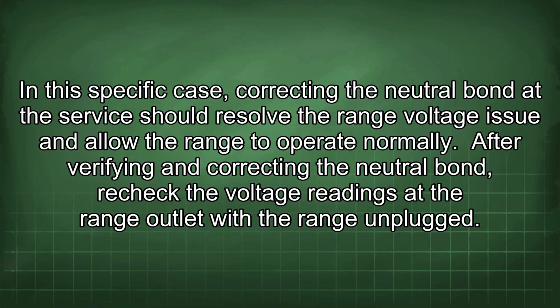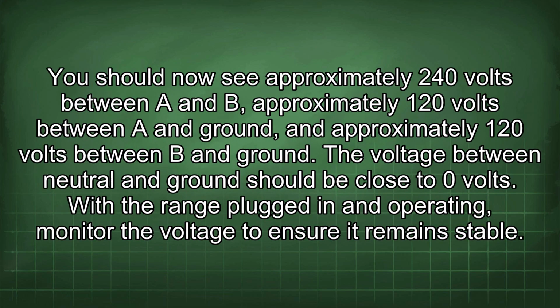range to operate normally. After verifying and correcting the neutral bond, recheck the voltage readings at the range outlet with the range unplugged. You should now see approximately 240 volts between A and B, approximately 120 volts between A and ground, and approximately 120 volts between B and ground. The voltage between neutral and ground should be close to 0 volts. With the range plugged in and operating, monitor the voltage to ensure it remains stable.